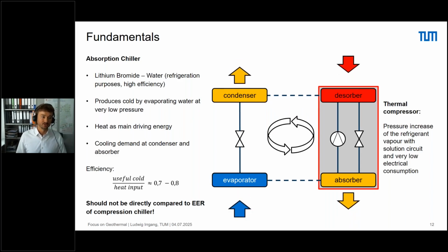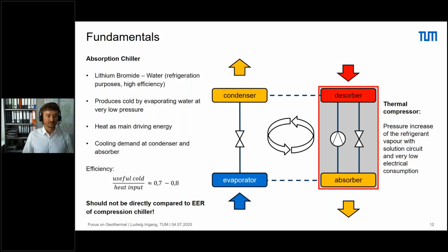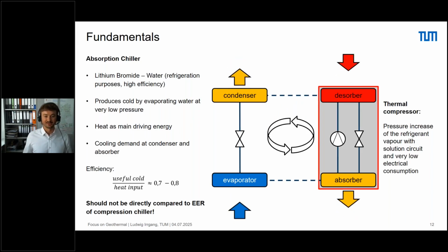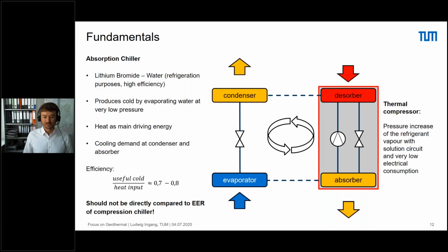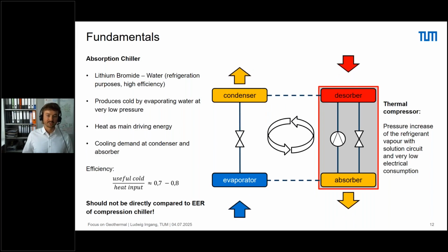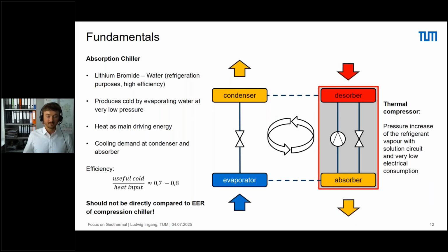Usually we use lithium bromide water as a working fluid for refrigeration purposes, since it gives us the highest efficiencies. With the cycle, we produce cold by evaporating water at very low pressures, and we can use heat as the main driving energy. On the right, you see the thermal compressor. Generally, this looks very similar to a classical compression heat pump or compression chiller cycle, but instead of the compressor, we have this thermal compressor. That means that we use heat as driving energy, but we don't have to use a lot of electrical energy because we have this pumping process instead of a compression process.